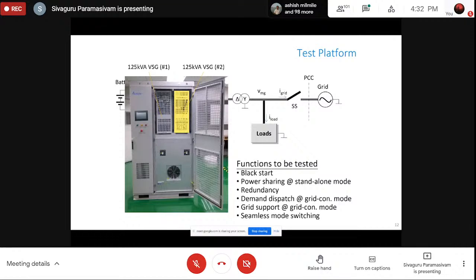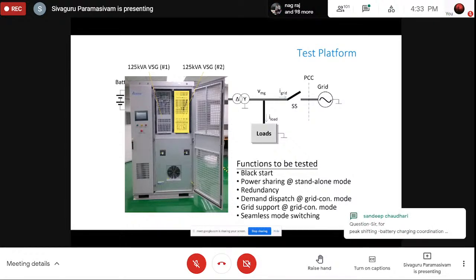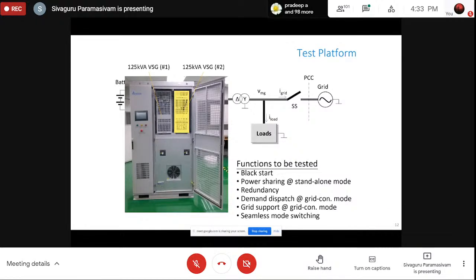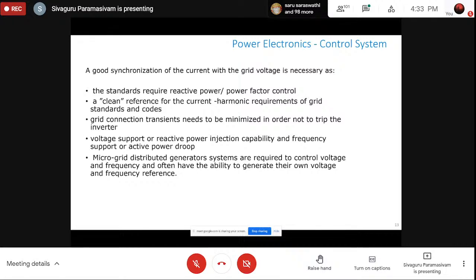And the most important thing is the last point you read, seamless power mode switching, which means that when we switch from the grid to the renewable asset, you will not even know that it happened. There will not be a flicker in the light. Even when you work on your computer, the computer will be uninterrupted. It is a completely seamless mode of switching, which in practice we have seen takes about 20 milliseconds to switch over from grid power to the renewable power, which is fine for all critical equipment, even some of the data center equipment. So let's talk about the power electronic control system. What is the requirement and what are the main things, because the power electronics and control systems are always integrated.